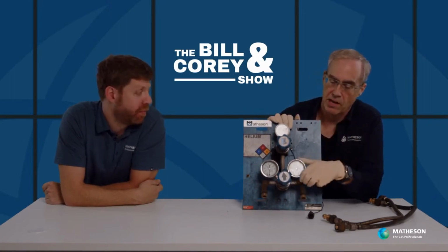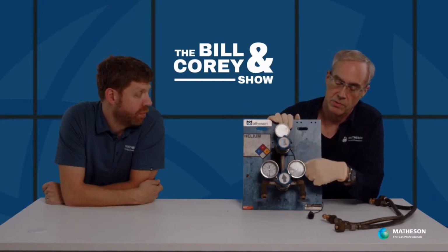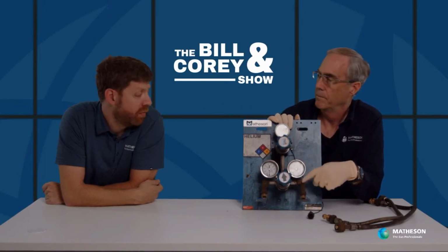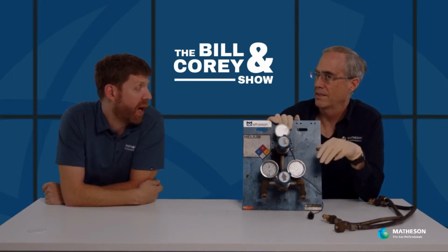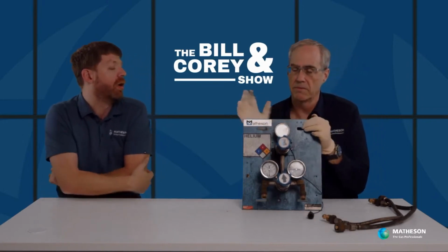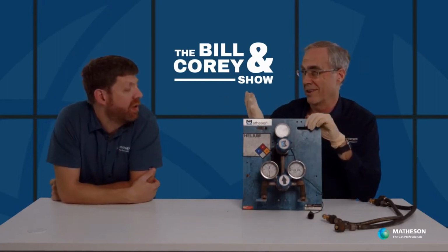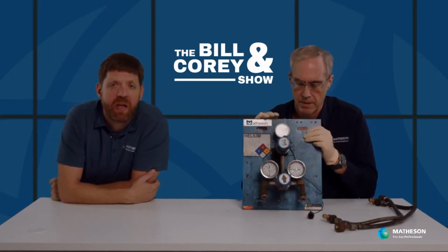You can tell our stuff is labeled with pressure ratings. So it says 3,000. And a good rule of thumb is anything brass above quarter inch, you want to double check it, because brass can get lower pressure ratings. Some fittings in brass at half inch are only rated to like 2,500. You really need to be rated higher than that. So it's just something to be cognizant about.